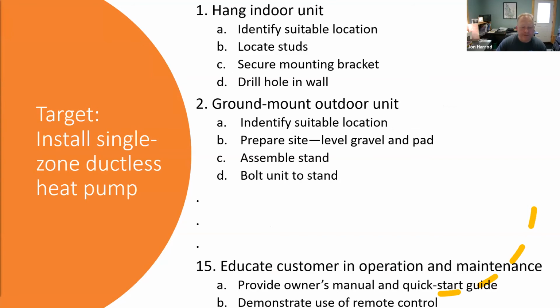So this is an example of our target performance level: to install a single zone heat pump. Our component tasks are things like hanging the indoor unit, and within each of those there are specific skills. We need to know what is the suitable location, locate the studs so our piping holes don't hit them, and know how to secure the mounting bracket accordingly.